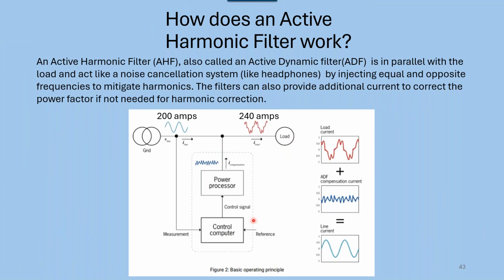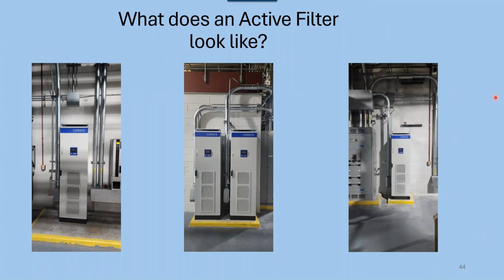What's a bonus of this is that because I've got capacitors in here, I've got one application right now where, when we did the study, it turned out we had 0.6 power factor, terrible power factor. Well, if I don't need to use all the capacitors for harmonic mitigation, I can actually use them to correct power factor. So the beauty of active harmonic filters is I can use them for power factor correction and for harmonics. On this one application, we decided to use about half of it for harmonic mitigation and half for power factor. We got the power factor up to 0.97 and used the rest for harmonic mitigation. So that's a real nice feature of active filters. Here's an example. This is actually down at Hartsfield Airport, where I've got 4 of my ComSys active harmonic filters, and this is what the installations look like. They just sit there and run, and they've cleaned up the system dramatically, both from a power factor standpoint and from harmonics. So that's what it would look like, very clean.